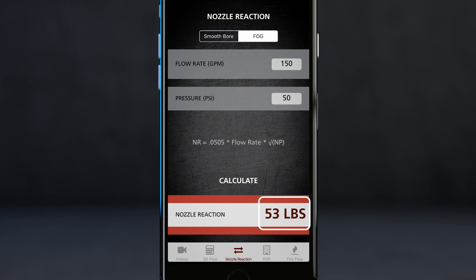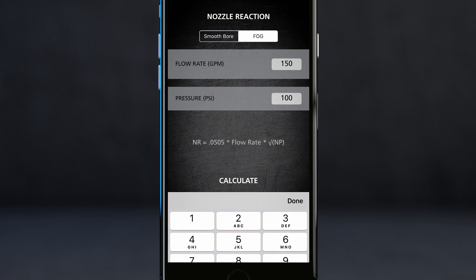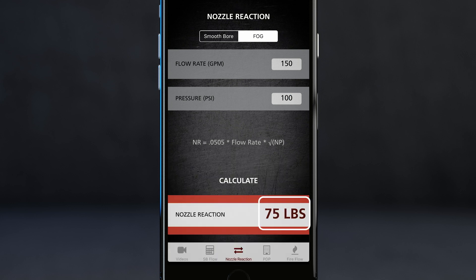If I wanted to compare that to 150 GPM at 100 psi, I simply take out 50, replace it with 100, hit calculate, and now that's 75 pounds force nozzle reaction.